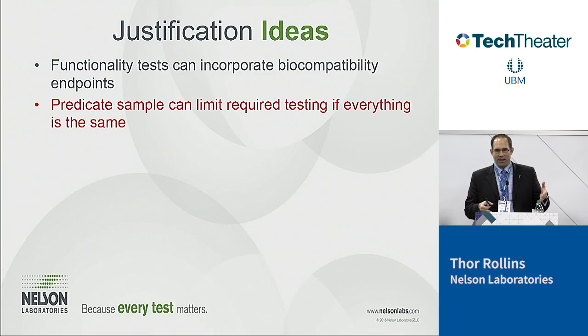There are a lot of endpoints that we can put into the functionality test that can address biocompatibility. Why not hit two birds with one stone and do some biocompatibility with the functionality tests? I'd be more than happy to get on the phone with you and work through that protocol to put in biocompatibility, even if you're doing it with somebody else. I just don't want to do unnecessary animal testing on the back end. So we can do hemocompatibility, some toxicity evaluations, some implant evaluations, all in the functionality tests, okay? So really consider that when you're starting to design a device: where can you put those biocompatibility endpoints?